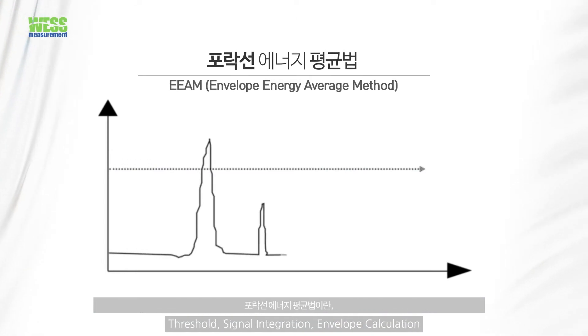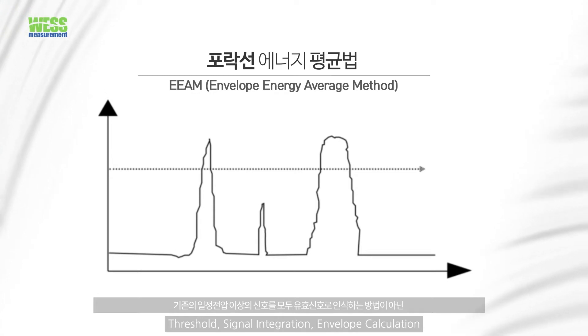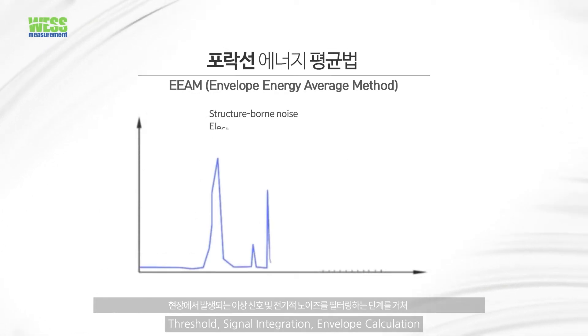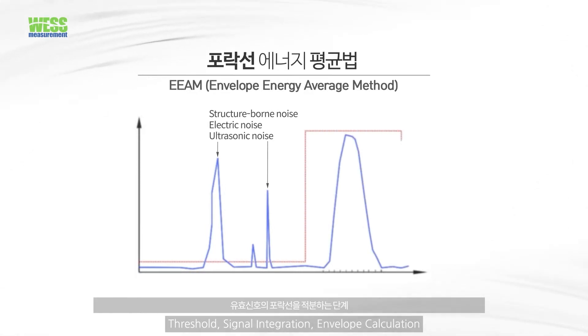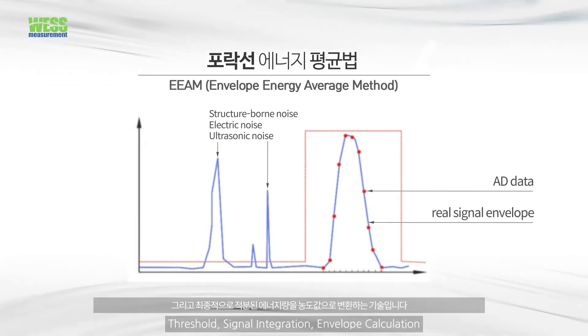The EEAM technology converts the amount of integrated signal to a density value after filtering abnormal signal and electric noise. This technology is different from the conventional ultrasonic attenuation method, which adopts all types of reception signal higher than a certain threshold voltage.